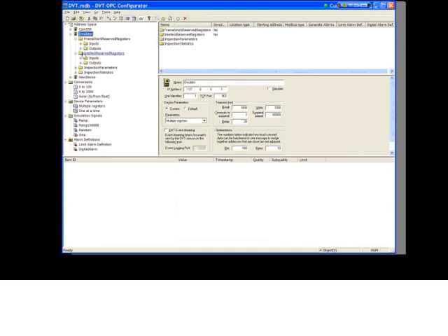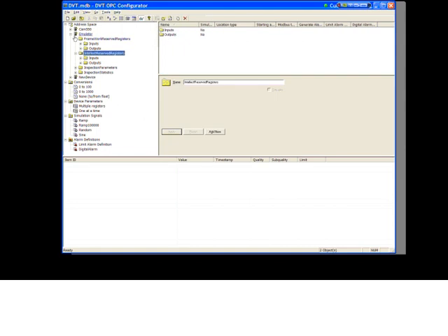In Intellect, you don't have to do that because it is clear on the Intellect side that you are writing to Intellect or to Modbus registers. And the OPC configurator knows where those are, and you can give the Modbus address straight as you see it in Intellect. But the Modbus address for Framework connections will be different than that register to which you're writing your data. And we'll do an example of this using Intellect.